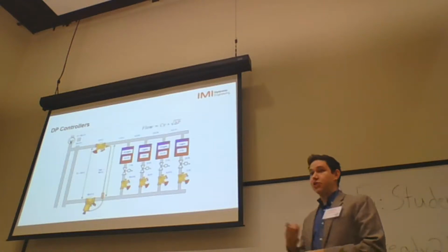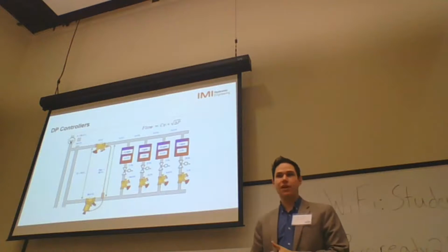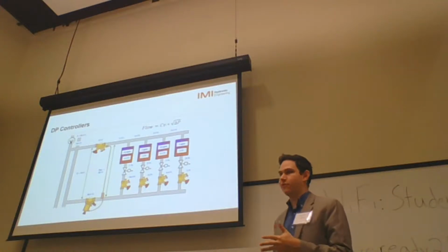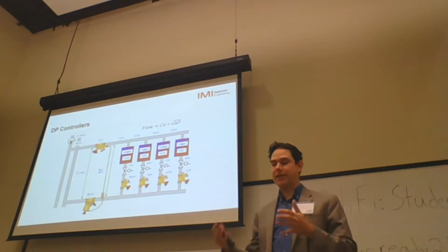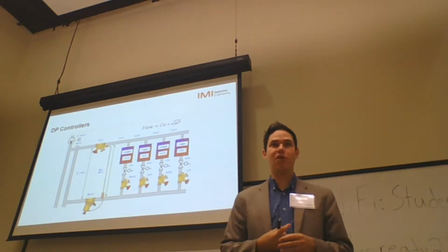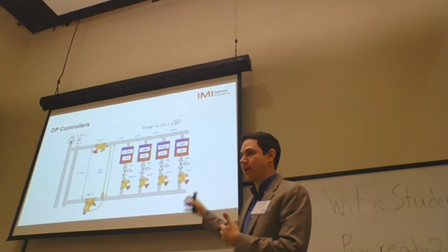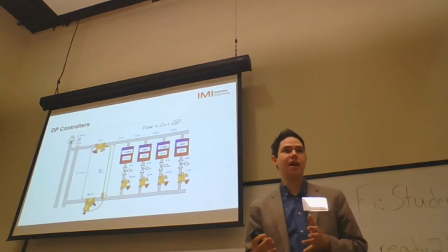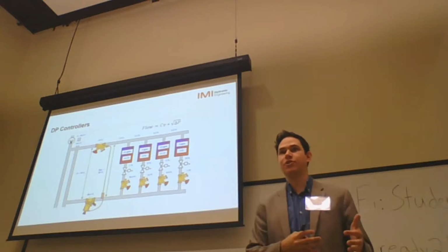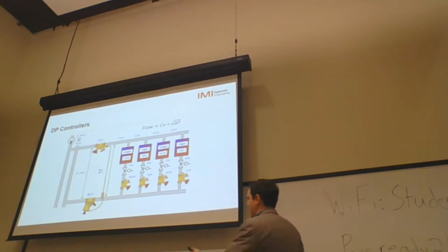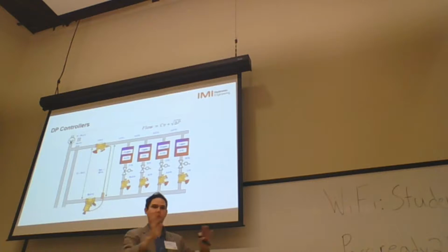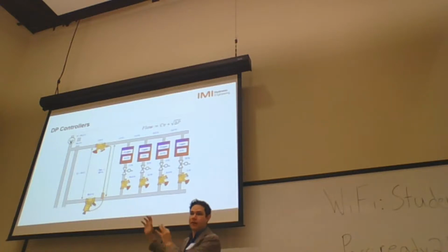So let's talk about the differential pressure controllers. This is a great helper for the TAB guys. It helps a lot on the commissioning, on setting the right flow rates, because it's a way to get a pressure independent branch. So as soon as you set the first branch in this installation, there are 4 units, and you set the differential pressure control of this branch, you can do whatever you want in the rest of the installation. It will never affect the branch that you set before.